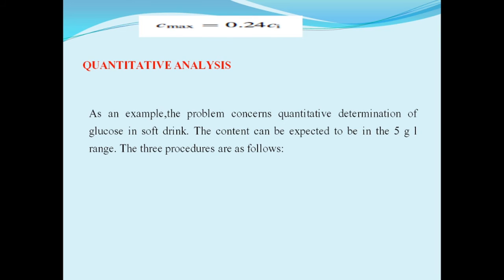The calculations are then not performed with simple rules of 3 as below, but by means of the calibration graph slope. Calibration graphs should be straight and run through the origin.